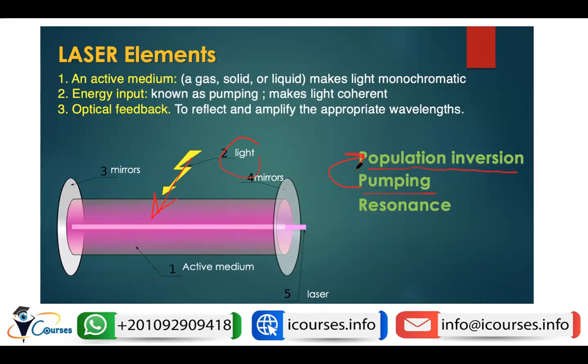So the electrons become more excited, and now they are traveling back and forth between the two mirrors, which is called resonance, in order to make the laser more coherent and more augmented. And then we allow the passage of the laser through one end. If this is through the partially transparent mirror, this is a continuous mode. If this is done through a shutter, this is the Q-switched mode. Is it clear?